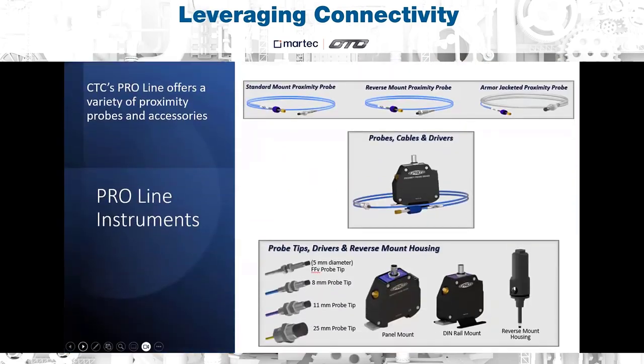So a full proximity probe system will consist of a probe driver. This is where you'll be providing power, and this will also be powering the rest of the probe circuit, an extension cable, and a proximity probe itself, as you can see over here on the left-hand side. There are specific lengths for proximity probe systems, the most common being 5 meters, 9 meters, or 1 meter in total length. That's just because that impedance reading that I was talking about earlier is so sensitive. We like to know all of the electrical characteristics of the extension cable and probe so we can just focus on the change in displacement.